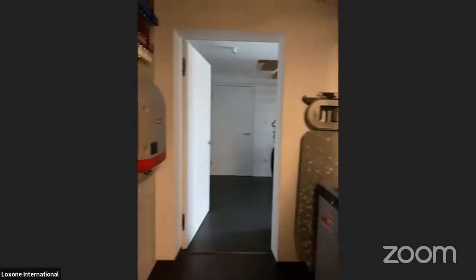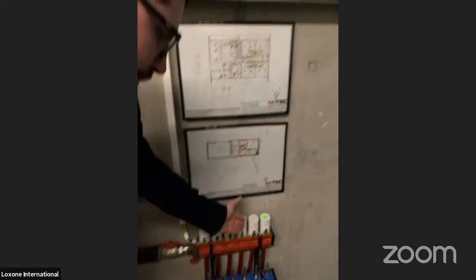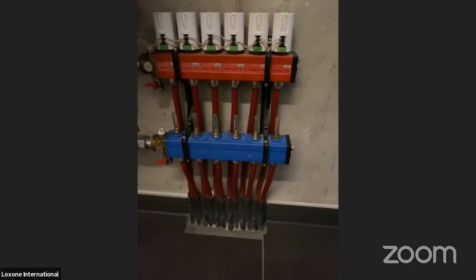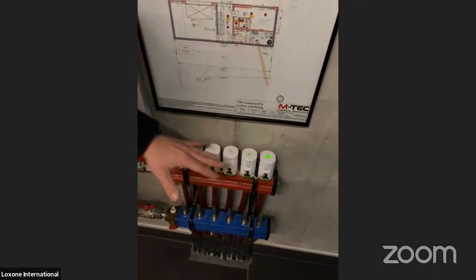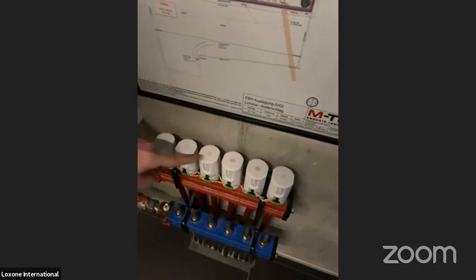In this house we have underfloor heating everywhere, and here we have a very deep integration of the system. Typically you have it on a room basis, like here. We have several different valve actuators, one for each room, like here room number 5, bathroom, and so on. These two are blinking red simply because we indicate whether water is currently flowing or not, so this doesn't mean they're not working. These are currently not heating because the temperature is fine, and these are open.